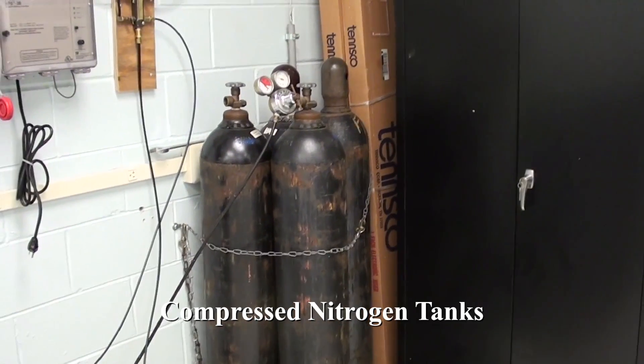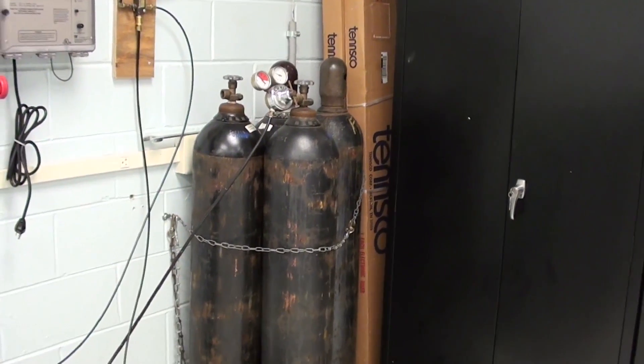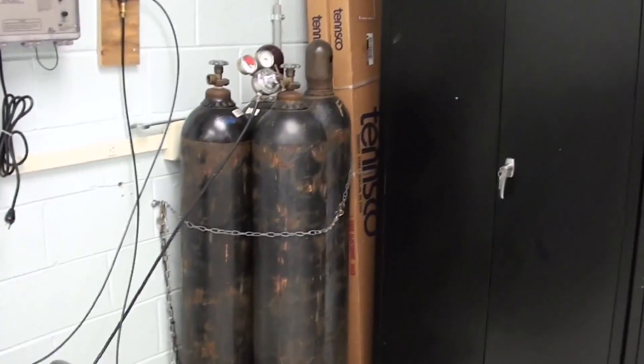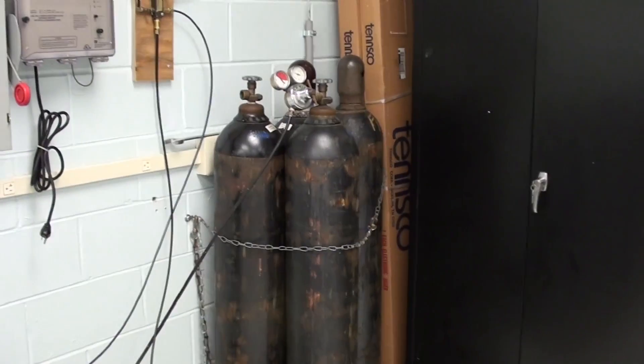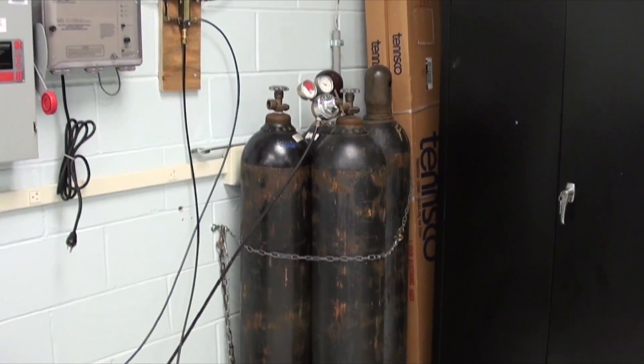And at those voltages, just a little bit of moisture can cause an arc. You've got moisture across an insulator and a little bit of dirt, it's not an insulator anymore. And 38,000 watts, you can figure out the voltage across the line if you want to figure out 50 ohms of that. It's a few thousand volts that can make quite a mess if it starts to heat.